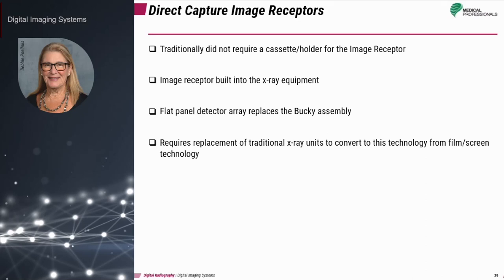Direct capture conversion systems were originally cassetteless systems, with the image receptor being an integral part of the X-ray unit itself. The flat panel detector replaced the Bucky assembly and was never touched by the technologist. Traditional X-ray units had to be replaced when converting from film screen to digital imaging. Today, there are wireless detectors that can be used with existing X-ray equipment.